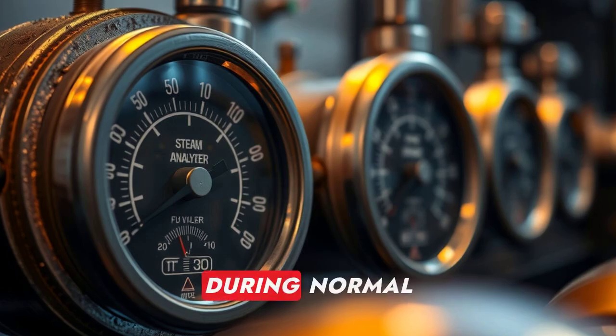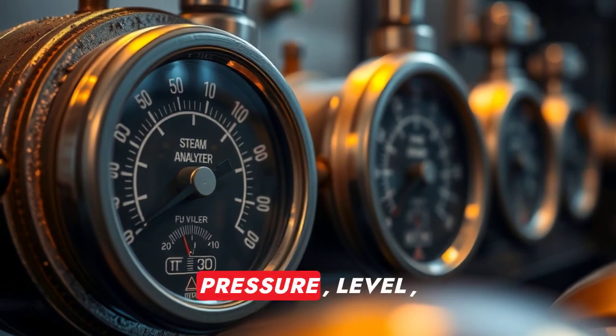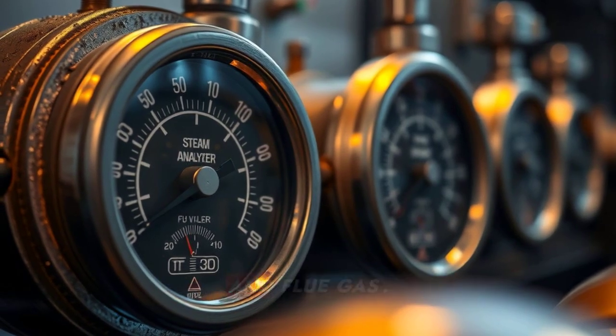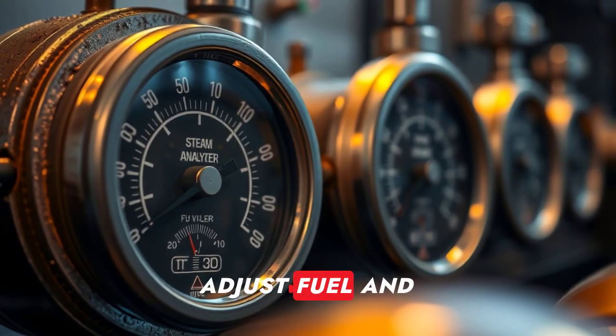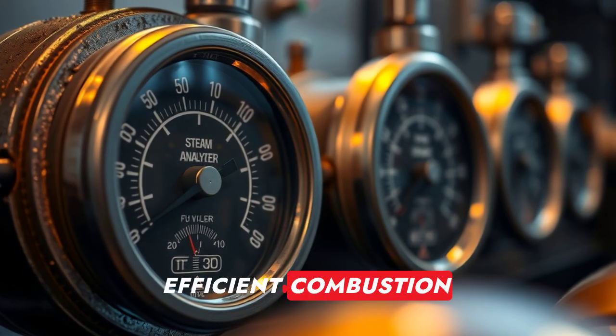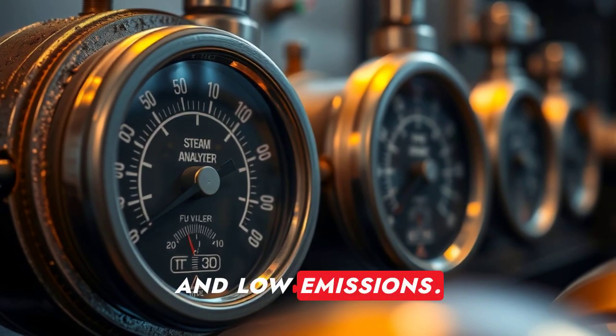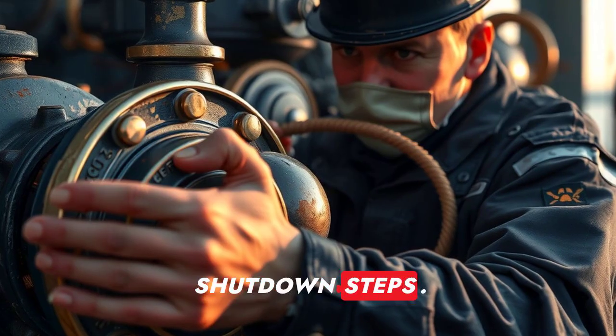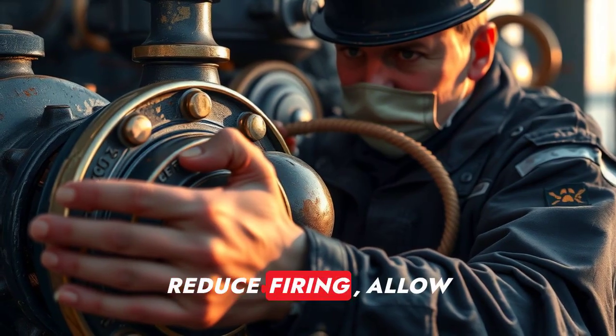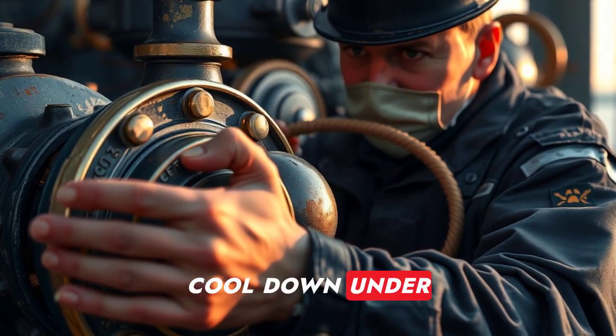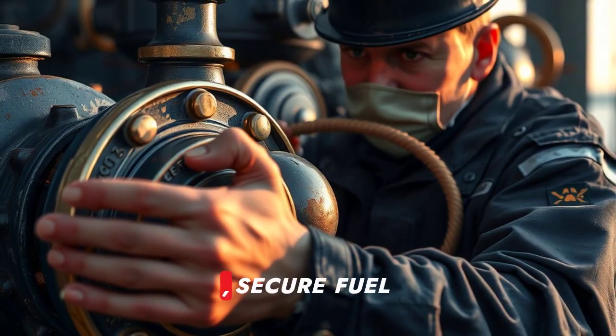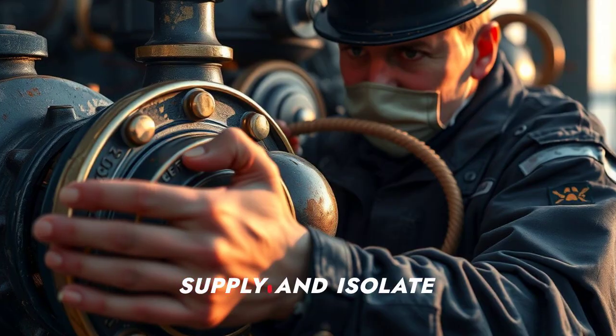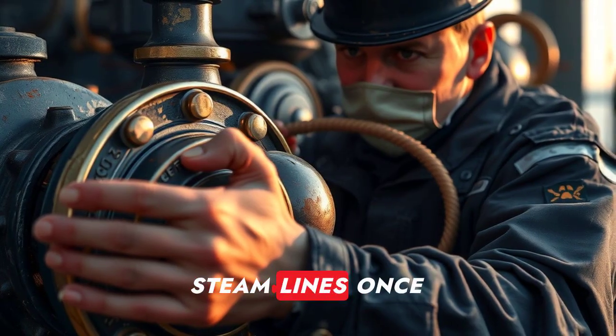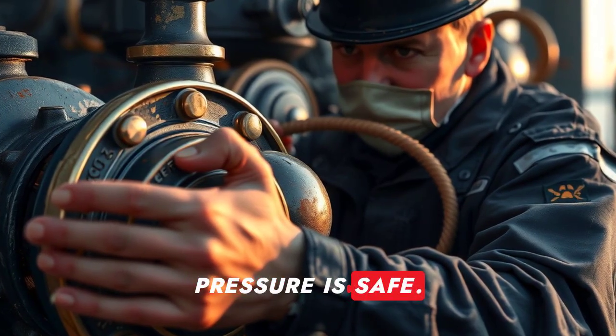During normal operation, monitor pressure, level, furnace temperature, and flue gas. Adjust fuel and air ratio for efficient combustion and low emissions. Shutdown steps. Reduce firing. Allow cool down under controlled conditions. Secure fuel supply and isolate steam lines once pressure is safe.